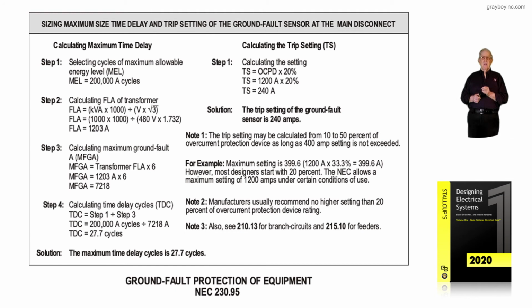Then the example says the maximum setting, if we took 399.6 and multiplied 1,200 amps by 33 1/3 to get that, that's where the 400 amp setting comes from with a main overcurrent device rating of 1,200 amps under certain conditions of use. And then note 2 says the manufacturer usually would recommend no higher setting than 20% without them sending somebody out to see it. And then they may want to send somebody out to see it anyway. So you would contact them. And notice we've already talked about note 3.